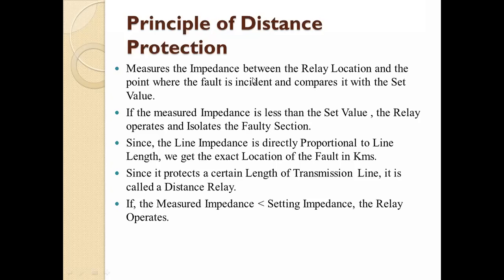The impedance of that relay is fixed, meaning it is preset. If a fault occurs and the impedance of that line varies, just tell me - if it is less than the set value, then your relay will operate. Or if the impedance is more than the set value, then your relay will not operate.